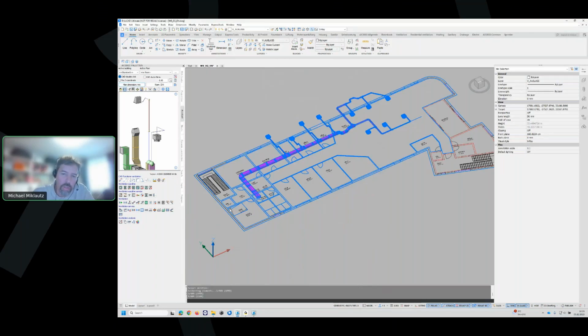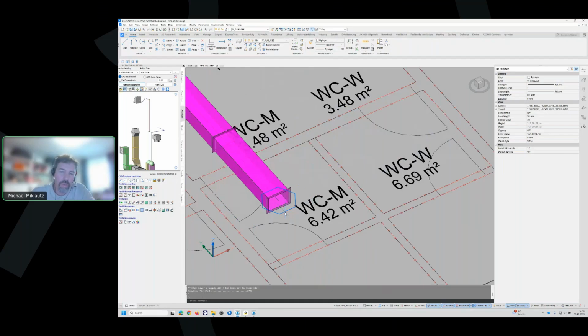Or if I now need a variant with more round pipe, I always have the possibility of doing a bill of material. As I use maybe this parameter, I want to use spiral seam pipe. Maximum pipe size, now it was 200. So I grow the maximum pipe size. That doesn't mean that I get only 710 millimeter pipes, but it means the software will use pipe until this cross section, this round pipe is used, and then it switches to rectangular. As well as here, the maximum duct height was set to 250 millimeter. In the first version, the system was 600 millimeter width and 250 millimeter height.